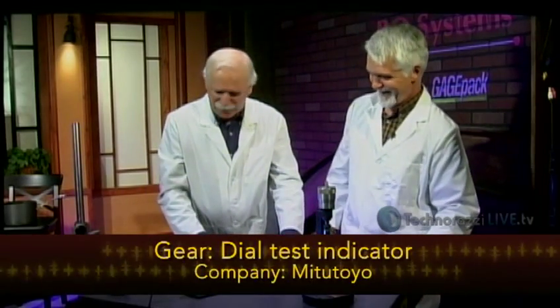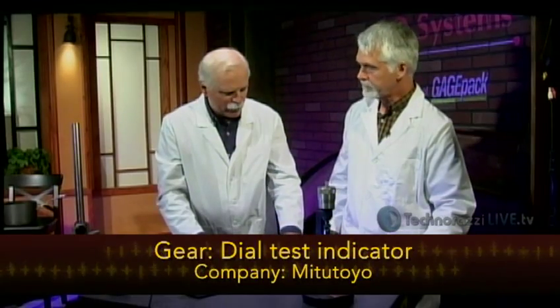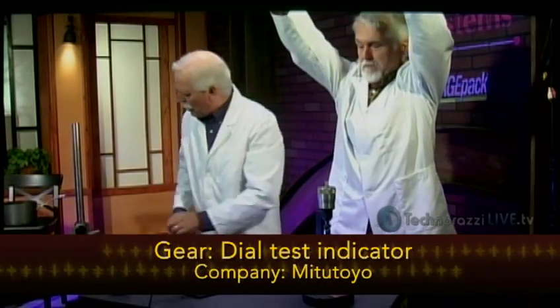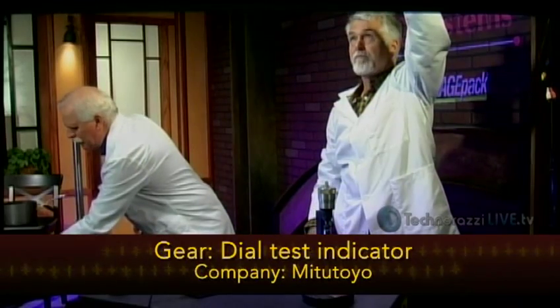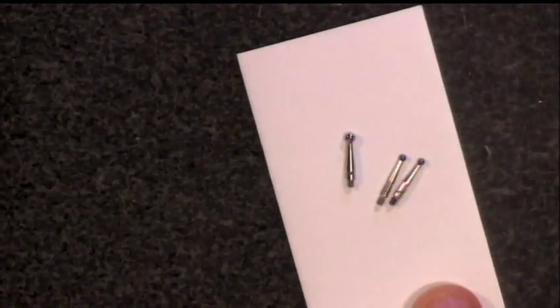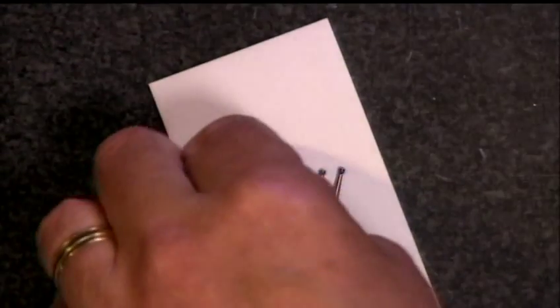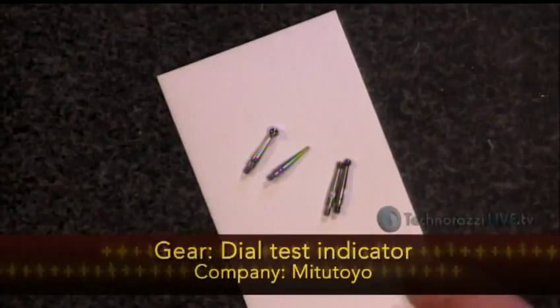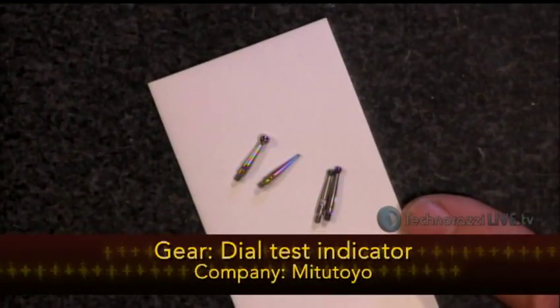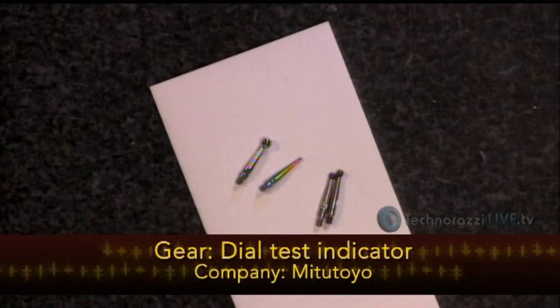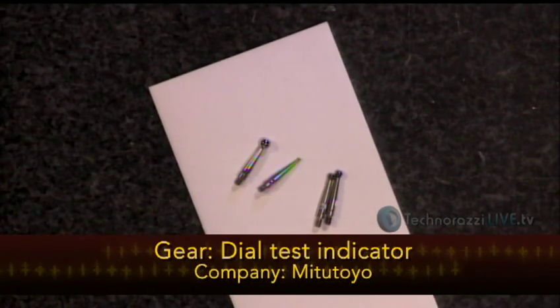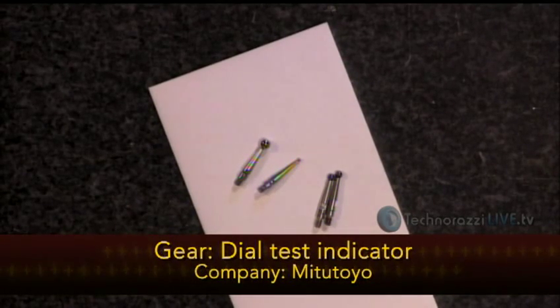The point I did want to make, though, is that, do we go to the overhead cam here first? Yeah, go back to the overhead cam. Within the same length, you can use different ball diameters. Those will all measure the same. They'll fit into different areas, which would be the advantage of using a different size ball. Right. Small ball, you can get into very thin areas. Large ball, it's a very stable measurement. Okay. So the ball diameter is interchangeable. Length is not.